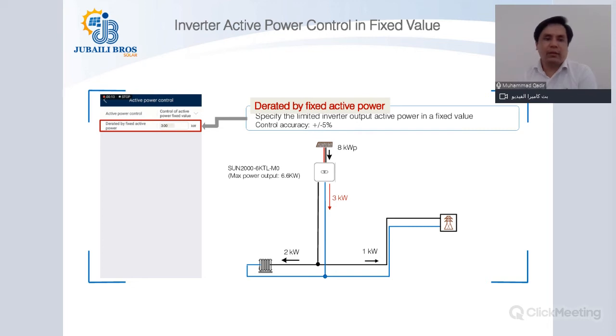Okay, inverter active power control on fixed value. Now, in the previous slide, we discussed the limitation of the inverter in terms of percentage. In this screen, you see that we have the option of limiting the output power of the inverter based on the kilowatts that we want. Let's suppose you have a 50 kilowatt inverter, you want to limit its output to 30 kilowatt. So you will put 30 kilowatt here, and thus the 50 kilowatt inverter will act as a 30 kilowatt one and will not let your PV plant generate more than 30 kilowatt.